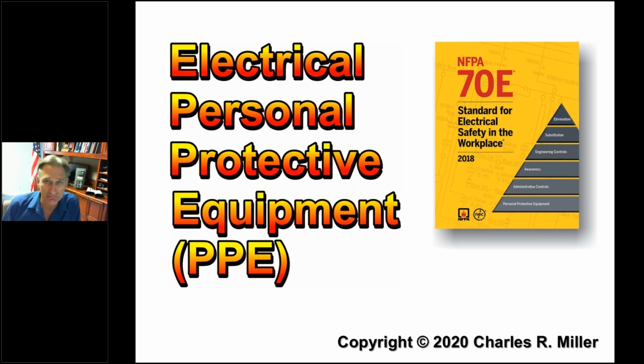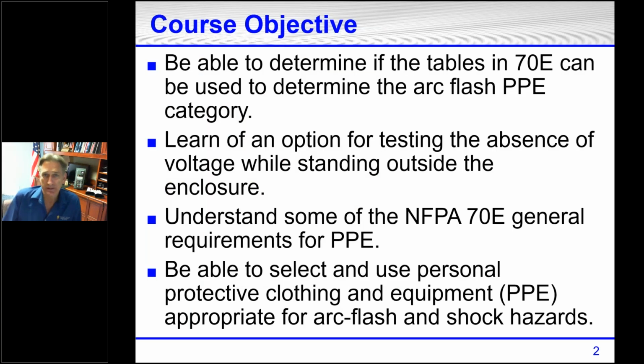We have a lot of material to cover in this 1 hour webinar: electrical personal protective equipment, and all this information is based out of NFPA 70E, Standard for Electrical Safety in the Workplace. The objective today is to be able to determine if the tables in 70E can be used to determine the arc flash PPE category. I'll show you which tables we might be able to use, and I'll give you the information as far as, all right, we can use it in accordance with this or not in accordance with that. We're going to learn an option for testing the absence of voltage while standing outside the enclosure.